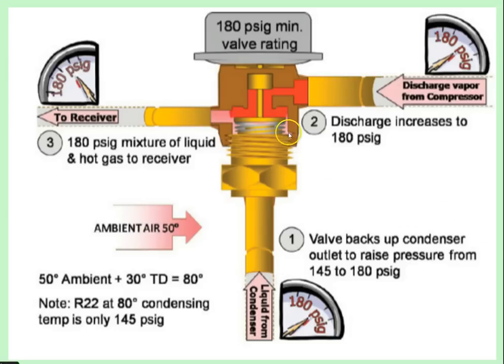Let's look at this HPR valve - head pressure regulating valve. It has a dome up here with a 180 PSIG rating. This is the liquid coming from the condenser, this is the discharge line from the compressor, and this is your liquid line that goes to the receiver and ultimately to the metering device. During normal operating conditions in the summertime, not low ambient temperature conditions, the liquid from the condenser is above 180 PSIG and opposes the force of the dome. The pressure from the liquid opens this seat, so liquid shoots right through to the receiver and out to the metering device, operating just like a system without the head pressure control valve.